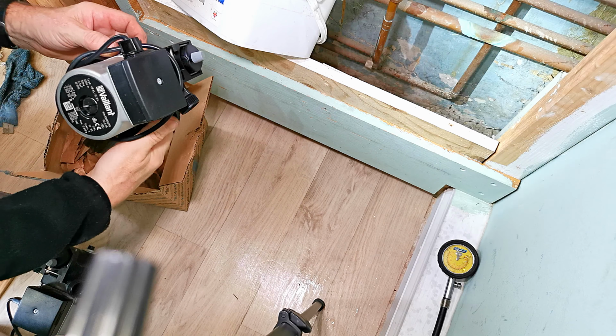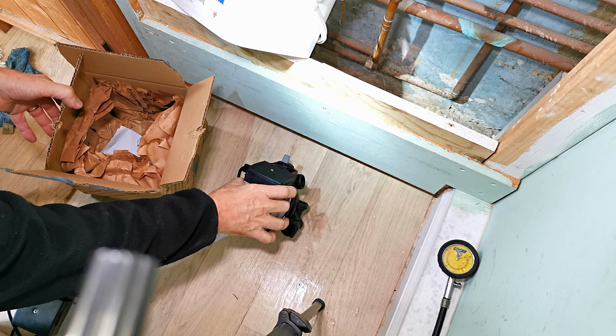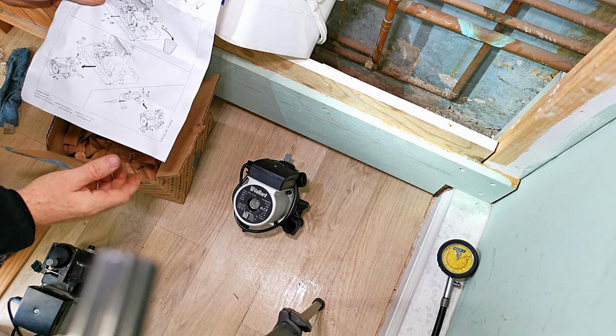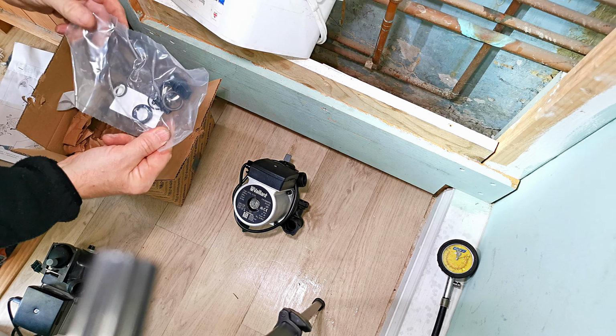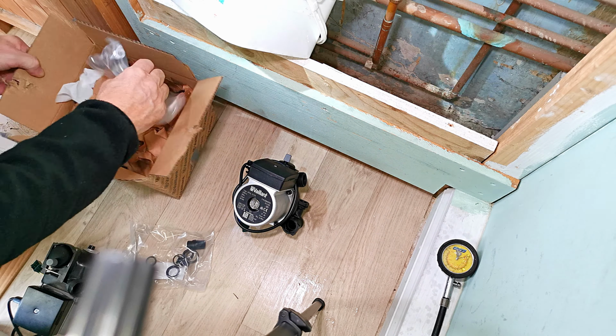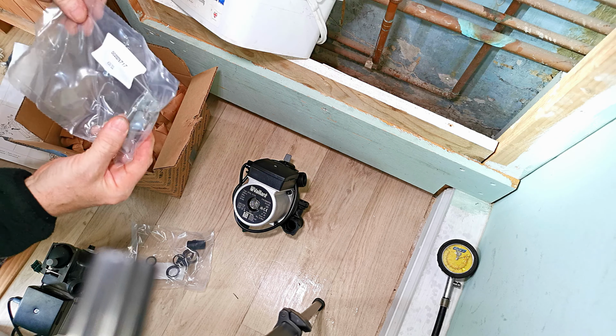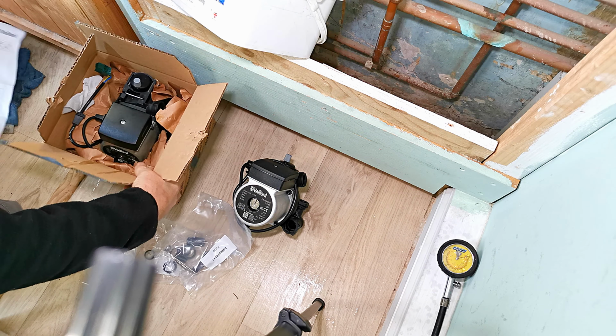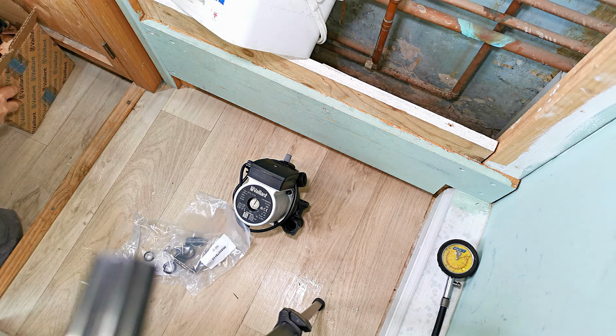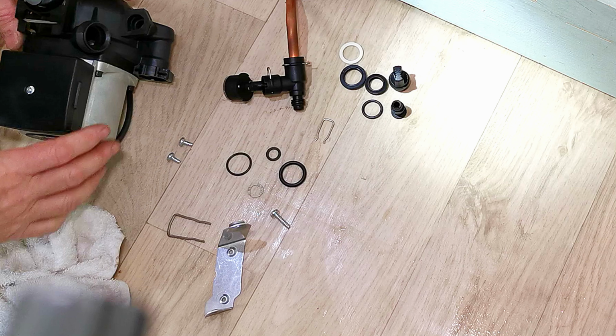So inside my new pump box, I have the pump. There's also some very basic instructions. We have all the new seals and O-rings, and there's also a new bracket and some screws. Just put that old pump to one side now. Here's all the new O-rings and the new bracket. I'm not going to need all of them because I've not removed the diverter valve. All the O-rings at the top of the screen are for the diverter valve, if I've gone down the route of removing the diverter valve as well.